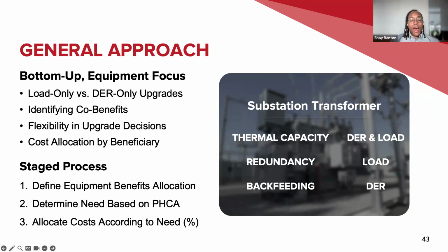There are also redundancy benefits. Having an additional transformer is often a load benefit, creating system resiliency to infrastructure failures, which is considered a load or ratepayer-specific benefit. Then there's backfeeding. Loads aren't backfeeding, right? So anything that allows a transformer to backfeed, enabling more DERs to connect, is a DER-only benefit. So even from this one substation transformer example, you can see categories and components that are both DER and load, as well as components that are load-only or DER-only.